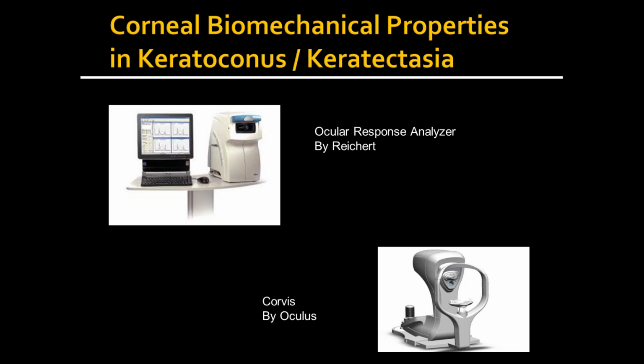One is the Ocular Response Analyzer, or the ORA, by Reichert, and the other is the Corvis system by Oculus, which is what we've been using over the past couple of months. And I need to tell you at this particular point, the software that looks at the biomechanical properties of the cornea through the Corvis system is yet to receive FDA approval. We hope it's in the near future, and once that happens, that can be released through anybody who buys the particular system right now.